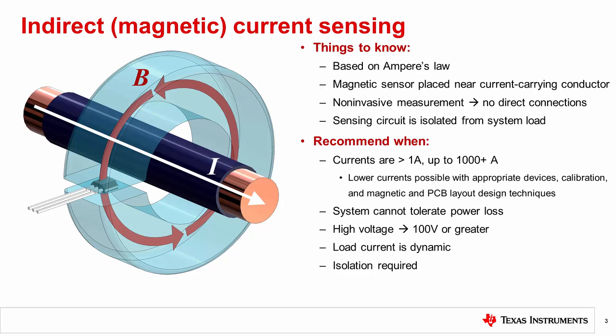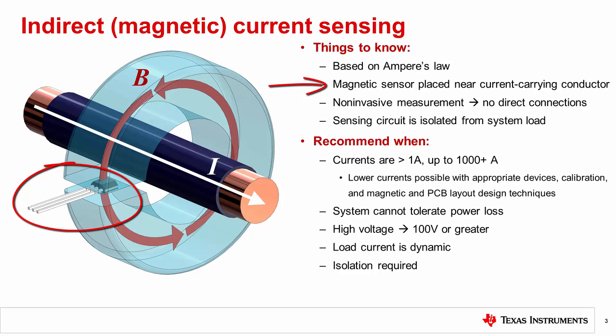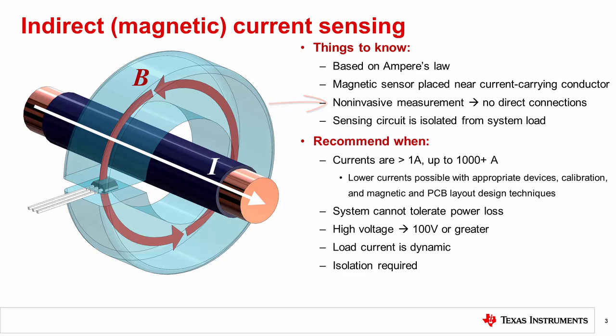Indirect or magnetic current sensing is based on Ampere's Law. According to Ampere's Law, the magnetic field in space around a conductor is proportional to the electric current through that conductor. By placing a magnetic sensor, such as a Hall sensor, near the current carrying conductor, a voltage is generated across the sensor which is proportional to the magnetic field seen by the sensor. This method allows for a non-invasive measurement where the sensing circuitry is not electrically connected to the monitored system. Since there is no direct connection between the sensing circuitry and the system, the system is inherently isolated. This makes magnetic current sensing an excellent choice for high voltage or dynamic current measurements.